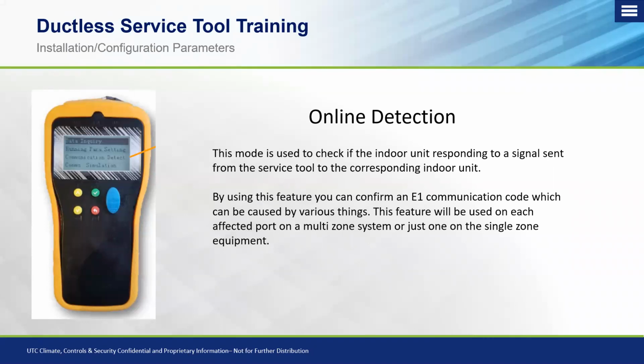We have our online detection feature on there. And again, this is in the communication simulation menu by selecting the online detection. So this mode is used to check if that indoor unit is responding to a signal sent from the service tool to the corresponding indoor unit. So by using this feature, you can confirm an E1 communication code, which can be caused by various things.